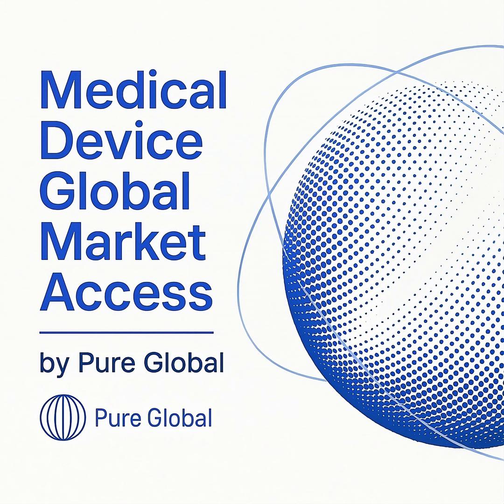A primary area of scrutiny, especially under the European Union's Medical Device Regulation, or MDR, which took full effect in May 2021, is the Clinical Evaluation Report, or CER. Notified bodies frequently find that safety and performance objectives are too vague. Instead of stating a goal to demonstrate safety, you must define specific, measurable outcomes with clear, justified acceptance criteria.